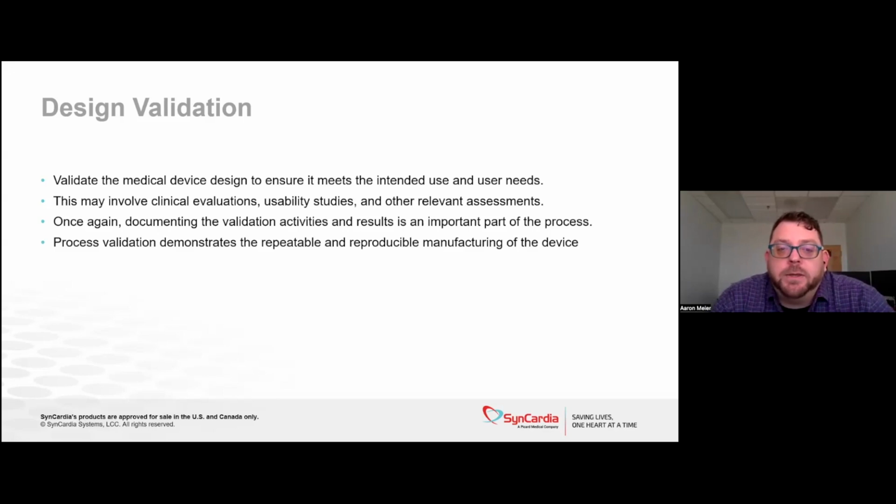This is where we get into things like your clinical study, where we potentially have to put the heart in patients and monitor their progress in an active clinical study. Maybe this is where we do usability studies, right? Where we give the patient the device and let them use it in a controlled environment with controlled expectations. So this is the part where we demonstrate that this device is suitable for its intended use in intended use environment for that intended use patient population. Right, this is where we demonstrate we actually have a medical device.